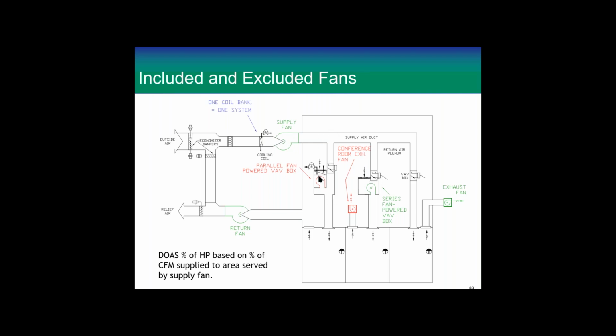Then if you go down the duct and you go through a parallel fan powered box, this box only runs in heating, which is not considered design conditions, so you don't have to count it. If you have a churning fan, say supplying a conference room, but the air does not leave the room, we don't require you to count that. If you have an exhaust fan that leaves the building, we require you to count it. And if you have a return fan that runs when the supply fan runs in normal conditions, then you have to count it. So all that horsepower adds together. If this was a relief fan that only runs in economizer mode or something, then you would not have to count it.